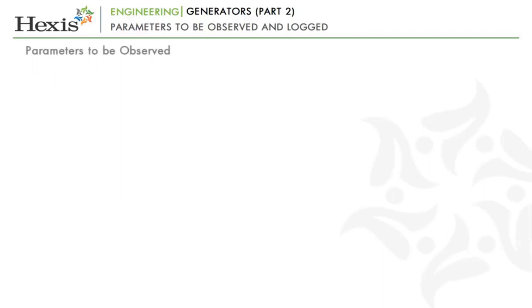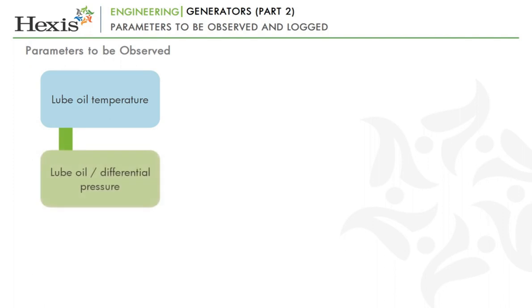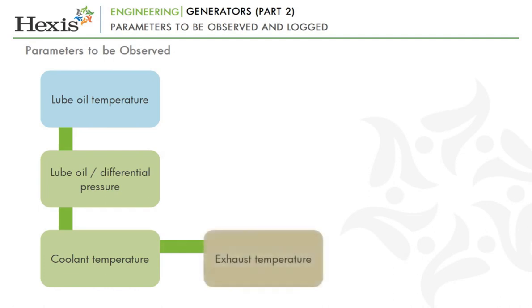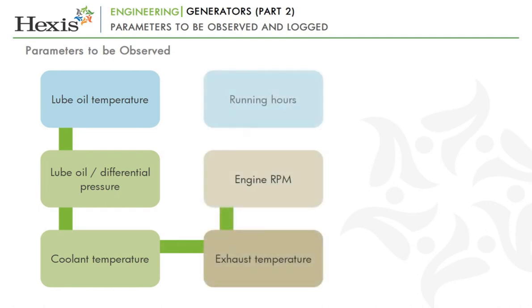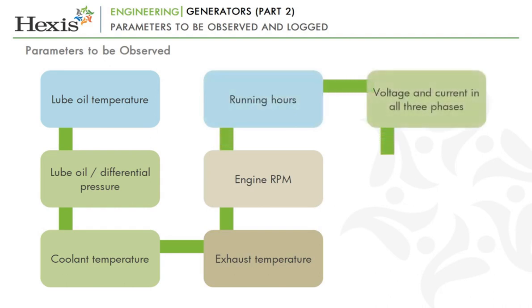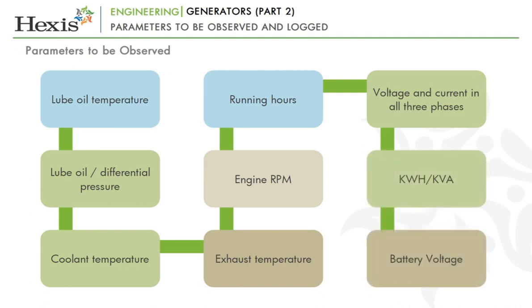While the DG is running, there are some basic parameters that should be checked and logged, which are as follows. Lube oil temperature, lube oil pressure or differential pressure, coolant temperature, exhaust temperature, engine RPM, total running hours, voltage and current in all three phases, kWh or kVA, battery voltage.